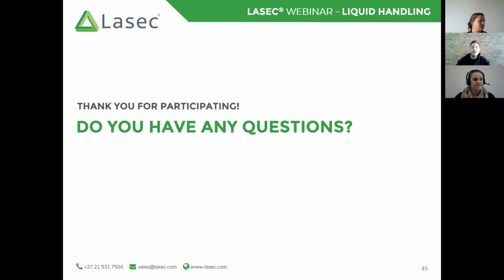All right. So like I mentioned previously, density, pressure, temperature, they all affect sample properties. So these need to be accounted for, and it's very often that in verifications, this is not a step that's accounted for. So when it comes to properly verifying or calibrating a pipette, we use what is known as a Z factor. So you cannot simply convert a volume measurement into a mass measurement. In order to go from a volume to a mass, it is important that you use this Z factor. And that Z factor is determined by the temperature and the pressure in the room, or those environmental conditions in the room at that time.